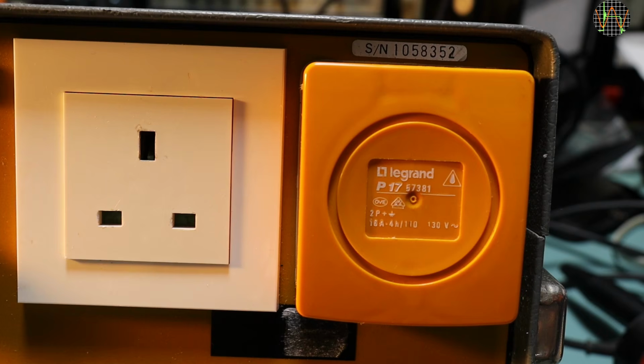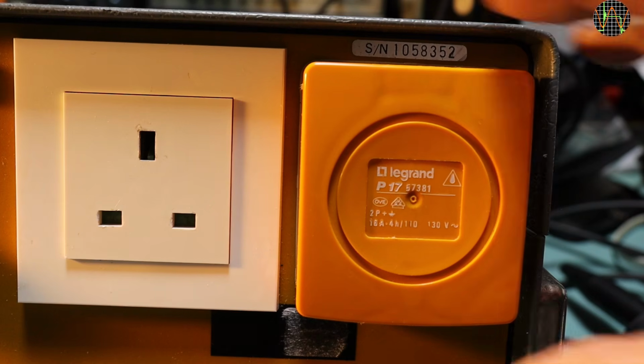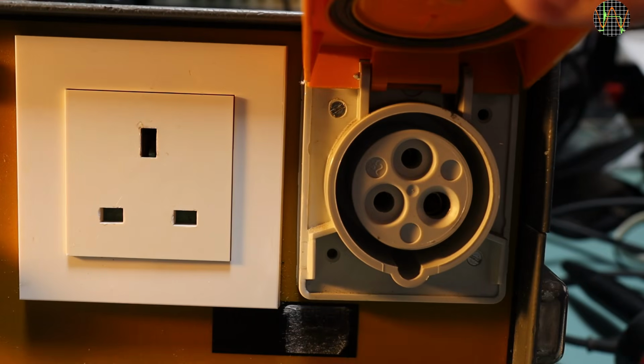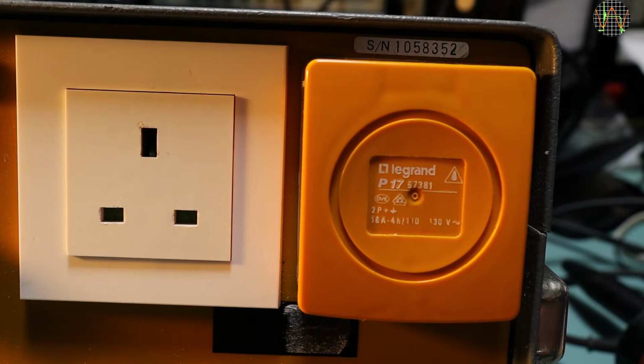The front has two power sockets. The white one is a standard socket for 230 volts AC. The one under the orange cover is a socket for 110 volts, which is occasionally used for electrical tools on construction sites because it reduces the risk of electrocution if the leads are accidentally cut or damaged. So this tester can be used for either 230 volts AC or 110 volts AC equipment.